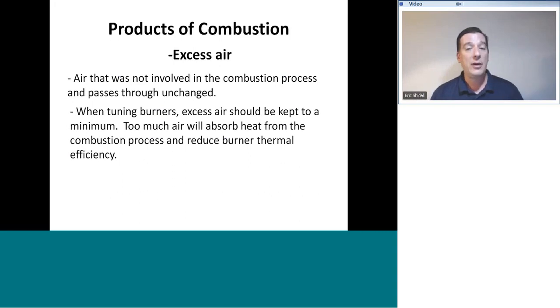This is important to realize that excess air is there because when we're tuning burners, too much excess air is just going to go right on up the flue. But instead, it's going to be heated by the flame. All the heat energy from the flame, we would like to get it into our conditioned space that we're heating. If we have a large amount of excess air just going straight up the flue, all of the BTU that it's taking with it are not able to be realized as heat in the house.